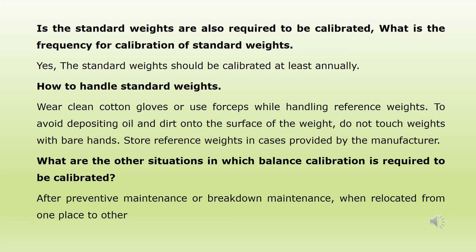What are other situations in which balance calibration is required? Calibration is required after preventive maintenance or breakdown maintenance, and when the balance is relocated from one place to another.